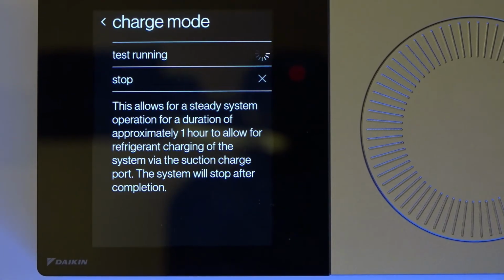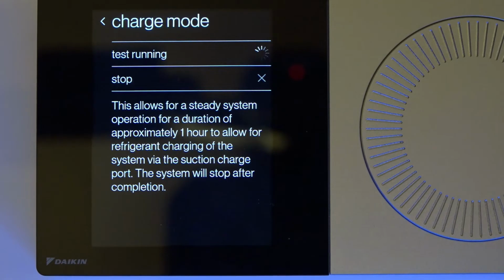I need to wait about 20 minutes and let this thing run so the EEV valves can open and close to move the right amount of liquid into the evaporator so the system can stabilize its suction superheat. Once the system stabilizes, then I can start looking at my subcooling number.